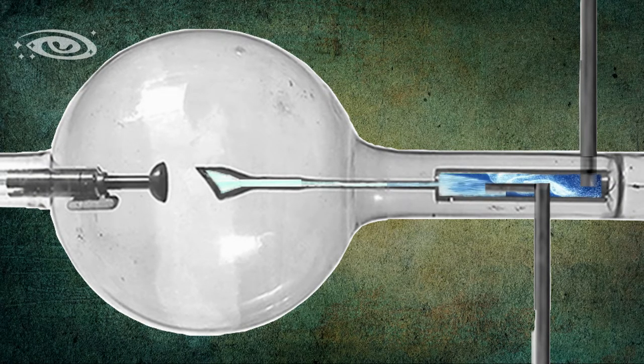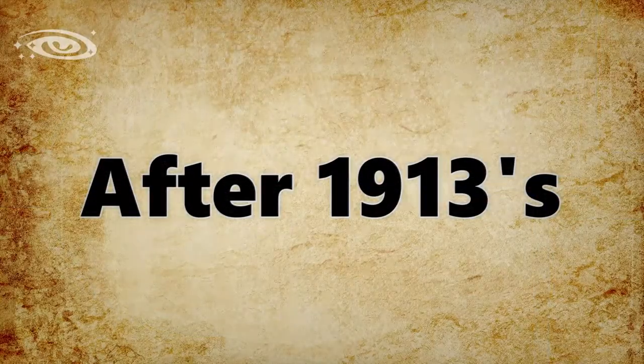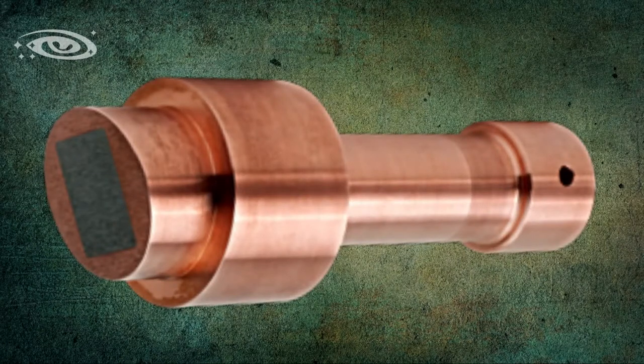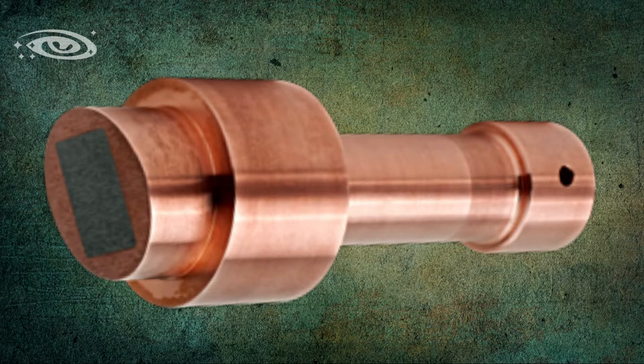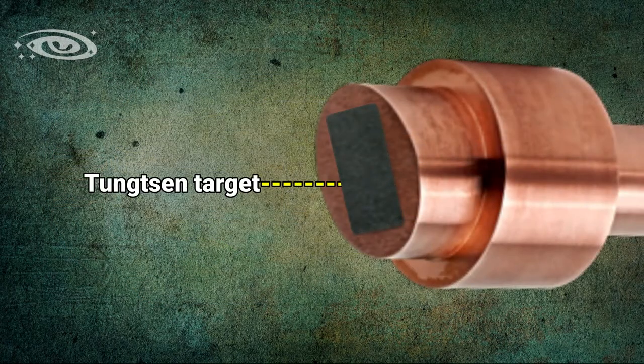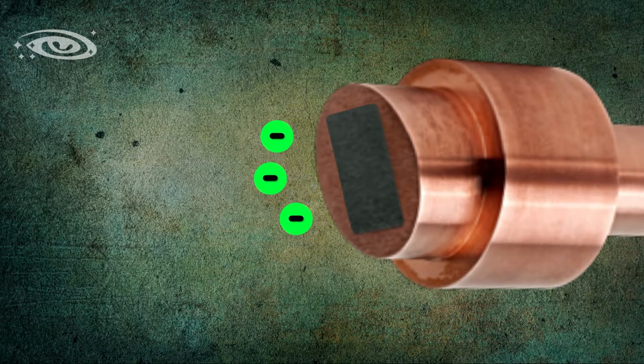And here the water cooling system is also very complex to do. So after 1913, they used copper blocks instead of water cooling system. Copper is a good conductor of heat. So copper is fixed inside this anode side and this target is embedded inside this copper block. So when electrons interact with the target, these copper blocks absorb the heat quickly from the target and increases the tube life and reduces the pitting.